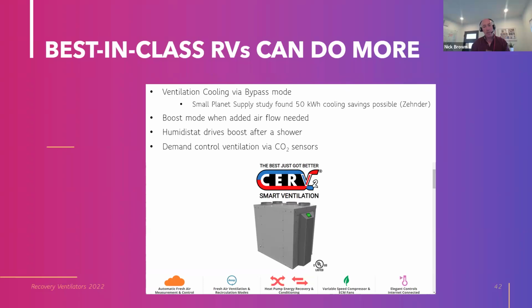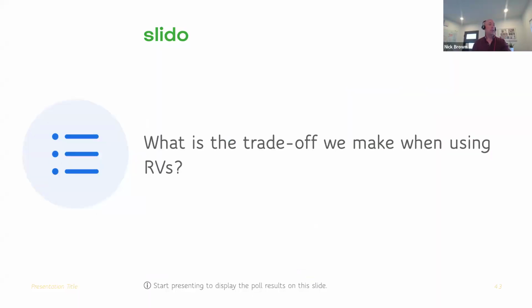But the top of the line recovery ventilators like this one, and again, we're not advocating any brands, I just like to cover real world in my classes. They can do other things like bypass mode, to the earlier question on, can you just bring in the cold nighttime air when that's beneficial? We found 50 kilowatt hour savings were possible using that bypass mode in the milder climate zones that have that diurnal swing. Others have a boost mode when added airflow is needed, either as measured by a humidistat for moisture level or as measured through a CO2 sensor. So all kinds of cool things these units can do.